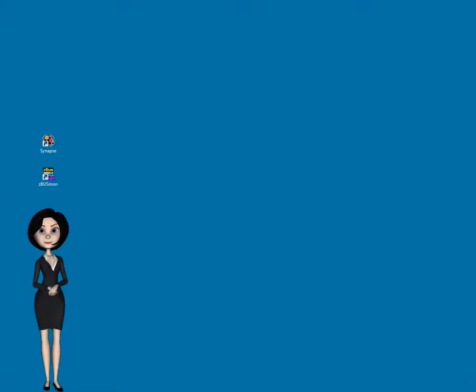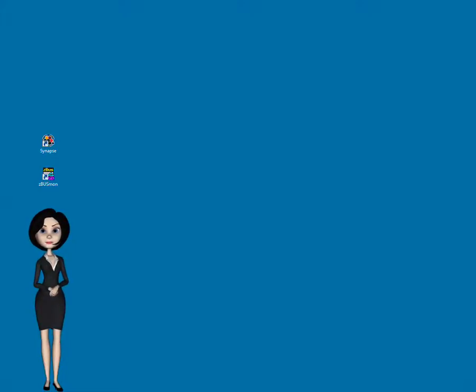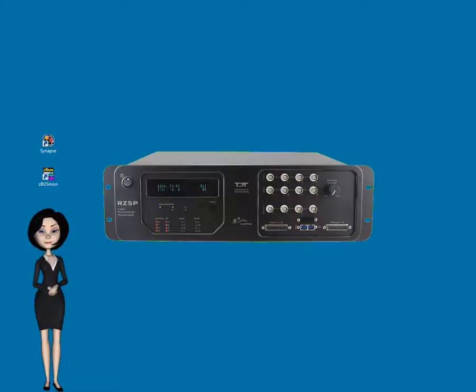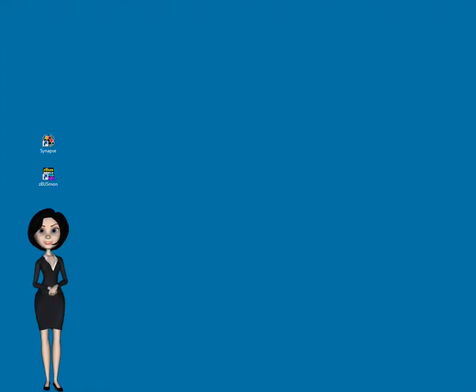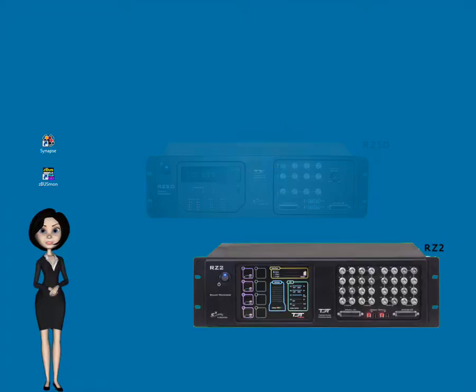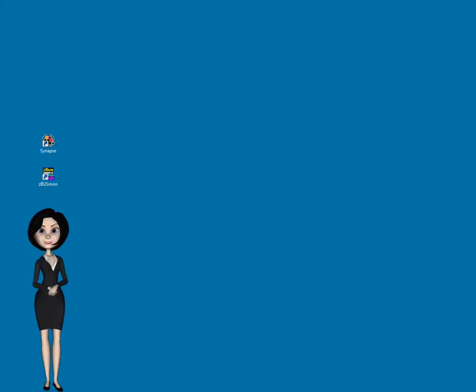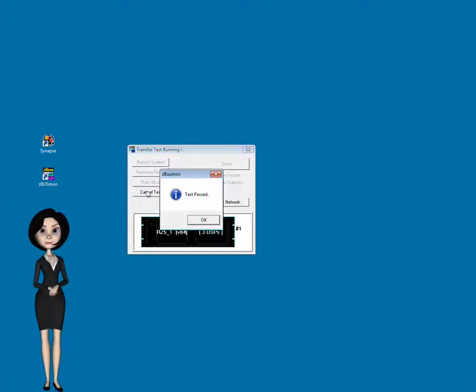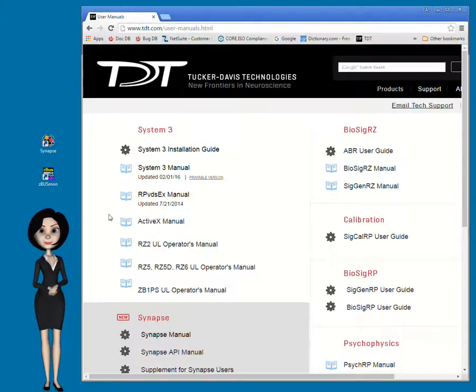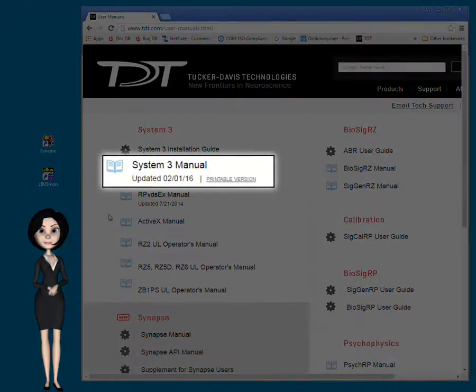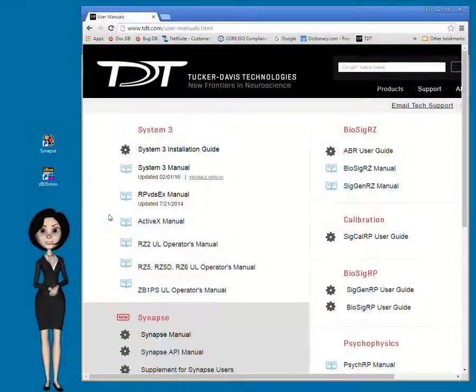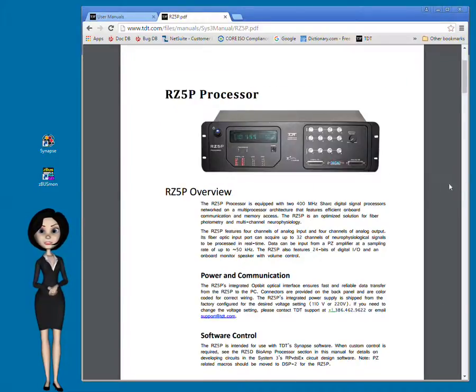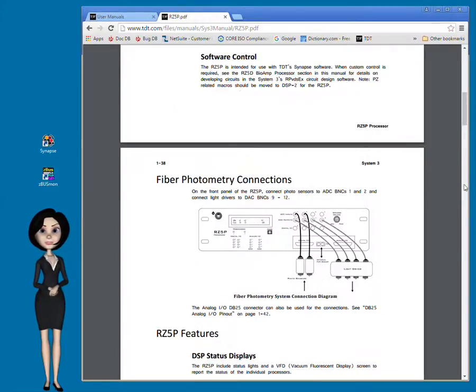Okay. Now you know a bit more about the hardware in your system. For example, you know whether you're using an RZ5P processor, purpose-built for fiber photometry, or another device suitable to this type of experiment. You also learned to use the ZBusMon utility to make sure the device is recognized by your system and to test communication. Now, let's use the System 3 manual on the TDT website to take a look at the final connections you'll need to make between the System 3 devices and the fiber photometry components.